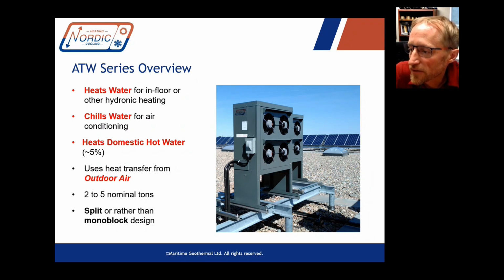Another reason to put multiple units is that even if there was a larger model size heat pump, if you only have single phase electrical power, then you'd be limited to the largest single phase model, which is going to be the existing ATW 75, like that 5 ton. There wouldn't be a single phase compressor that would be suitable for a larger model size. Usually houses only have single phase electrical power, so you'd only be using an ATW 75 anyway. The ATW2 that I mentioned earlier has 2 smaller compressors in it, so that might also be available in single phase. But in general, that's something to be aware of anyway.